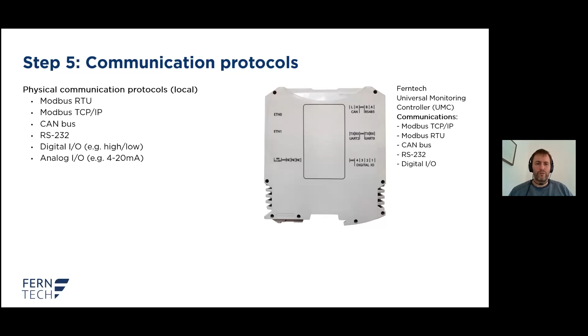That's probably one of the most important steps - once I know what to monitor and control, and I select the devices, it's all about making things communicate with each other. Communication protocols are one of the things that normally take more time to check, double-check, and test. At Ferntech we use a controller that has a large number of communication ports, covering almost all different scenarios you can find in a mini grid. If we need more inputs or outputs, we can always add more controllers in parallel.